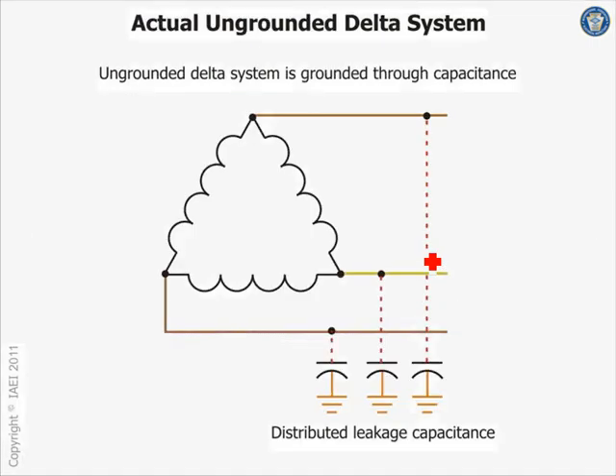And the last thing before I let you go, guys, here's an ungrounded system. Even if the system is ungrounded, it's actually grounded through a capacitive reactance, right? So even an ungrounded system is grounded through a reactance. What's a reactance? When you grab phase A, phase B, phase C, and you put them in a conduit, right? Don't you guys have, like I said, a capacitor?